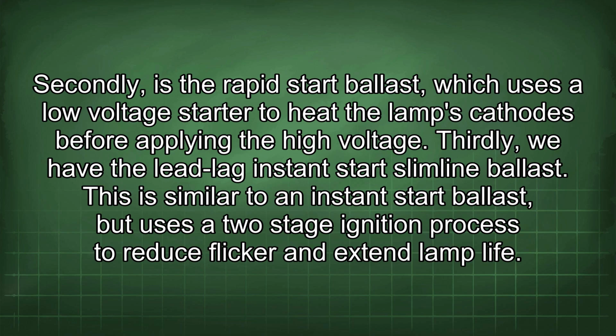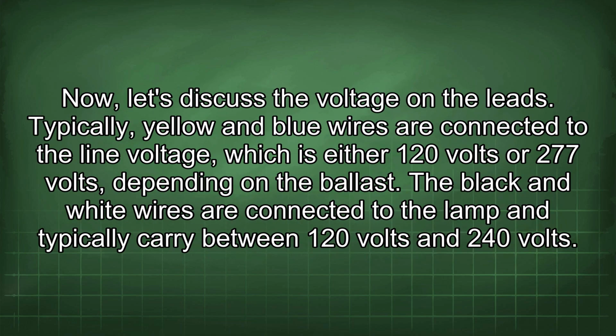high voltage. Thirdly, we have the lead lag instant start slimline ballast. This is similar to an instant start ballast, but uses a two-stage ignition process to reduce flicker and extend lamp life. Now let's discuss the voltage on the leads. Typically, yellow and blue wires are connected to the line voltage, which is either 120 volts or 277 volts, depending on the ballast.